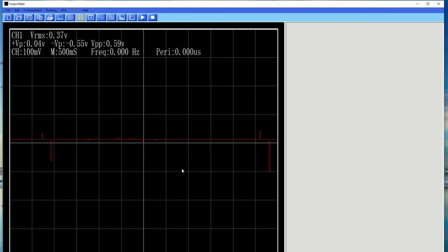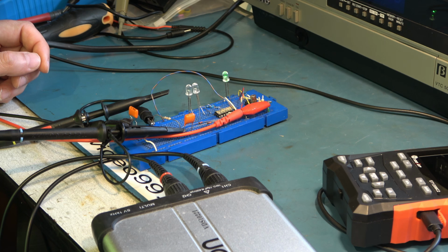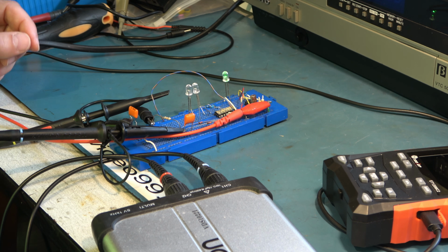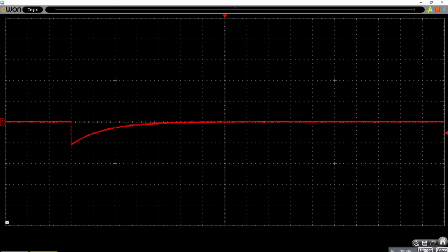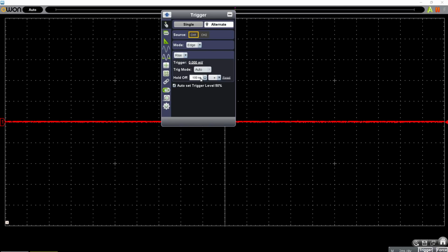Okay, next we'll have a look at the OWON oscilloscope and see if that does any better. So we're seeing a similar sort of result on this one. These occasional pulses flying by. Do we have any more options on the triggers? Yes, we could do hold off on this one. So we could potentially get it to trigger on the second pulse, but trigger mode is set to auto and it won't let us change because of the low sweep speed. So it doesn't actually get us a lot further on this particular waveform. Does the OWON do any better? It might have the potential to do better under certain circumstances, but not with this particular waveform.